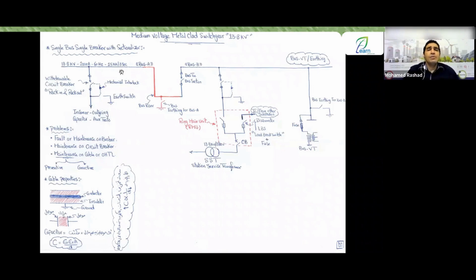Very good. Okay, so the first thing is I divided this bar into several parts, right? And then also, between each bar and the other bar. Now, engineer, if you still have a problem in one bar, you would now lose 1/3 of the station, I'll tell you, right? Instead of losing the entire station or losing 1/4 of the station, if you divided this bar into 4 parts as well. So engineers, very good. Okay, so let's continue.